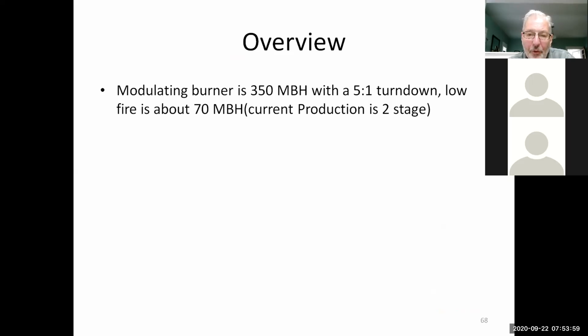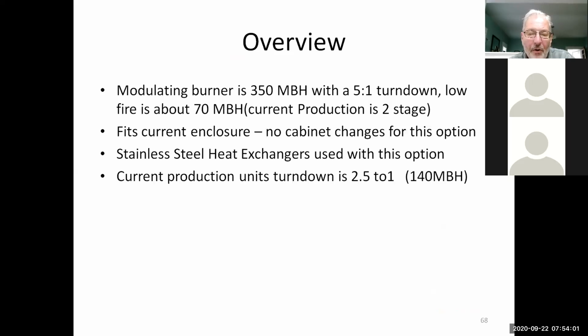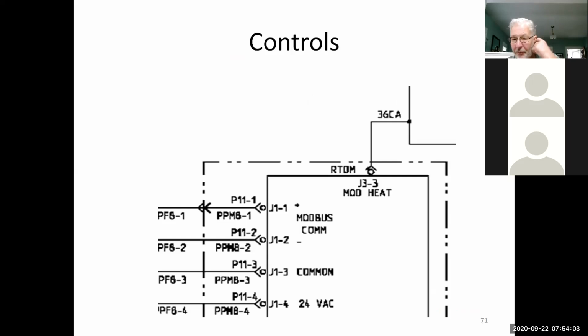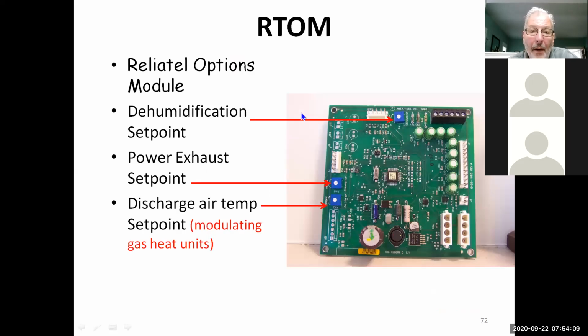Again, it's a 2-to-1 turn down ratio, and like I said, I wasn't going to spend a lot of time on it because we don't have a lot of them out there, to be honest with you. But if you do run into one, the temperature set point is controlled on the options module through this potentiometer right here.